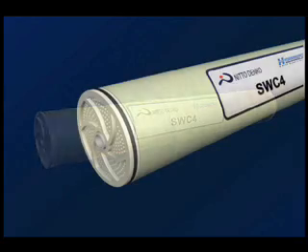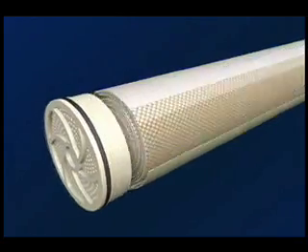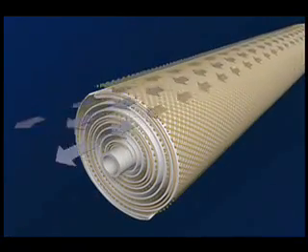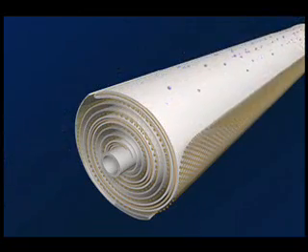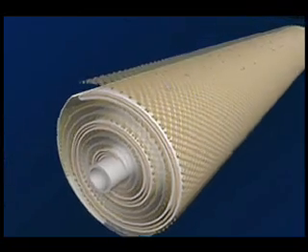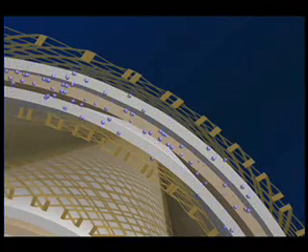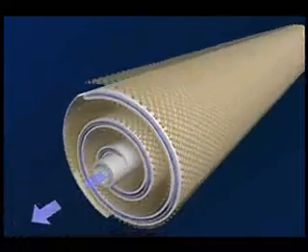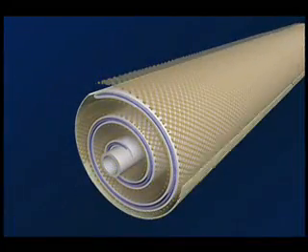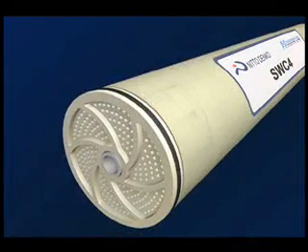With the back of the membrane completely sealed to the edges of the permeate spacer, the feed water is forced through the feed channel spacer contacting the front or barrier layer of the membrane. Clean water or permeate passes through the membrane surface into the permeate channel and then flows in a spiral direction to the center of the element and is collected into the core tube.